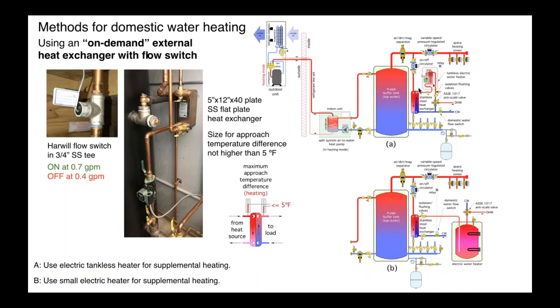Okay, one more. We actually did this in my daughter's house. This is an on-demand external heat exchanger with a flow switch. So here we've got a 5x12 plate size heat exchanger, 40 plates deep, and another portion. Well, let me explain this one. This pipe coming down, this is hot water from the top of the buffer tank coming into the primary side, and then it comes out, goes down through the circulator, and right back into the lower tank header, back into the tank.